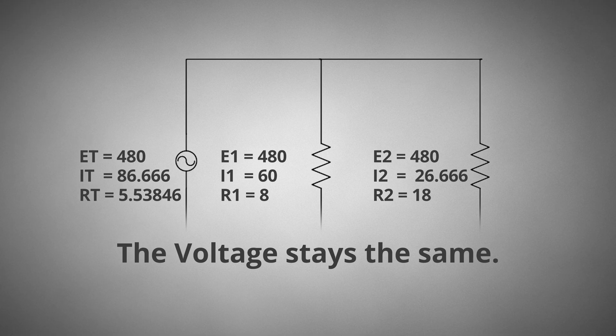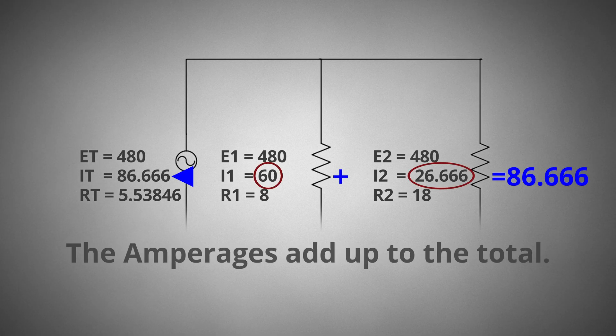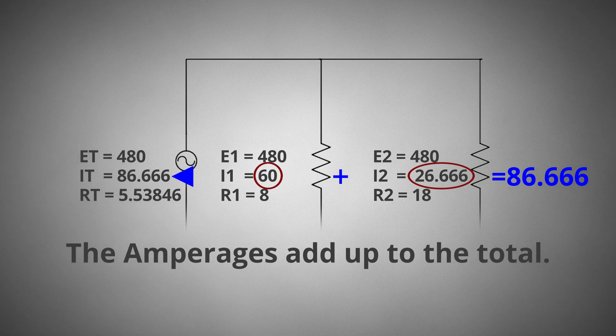As an electrician, parallel circuits are what we work on every day. If we were to test the voltage throughout any circuit, it would be the same. The amperages add up to the total. Parallel circuits have multiple paths for current to flow; therefore, the current in a parallel circuit is equal to the sum of the individual branches. In the field, we would add all the amperage together to size any circuit.